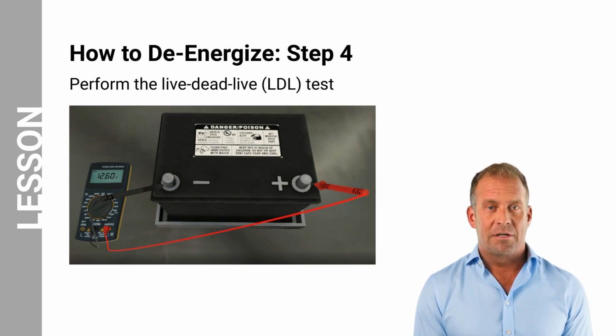Use tools and meters that are specifically designed for working with high-voltage systems. To perform the live-dead-live test, obtain a digital multimeter capable of measuring direct current, abbreviated as DC voltage. Set the digital multimeter to the DC voltage measurement mode by turning the knob to the appropriate setting. Insert the black test lead into the common, which is marked as the COM port on the digital multimeter. Insert the red test lead into the volts, which is marked as the V port. Turn the digital multimeter knob to the DC volt symbol.